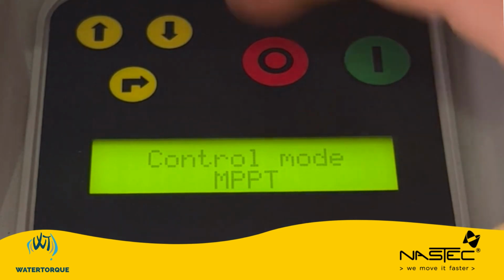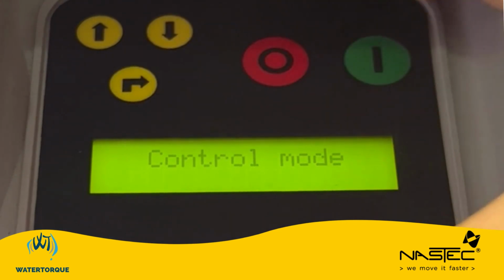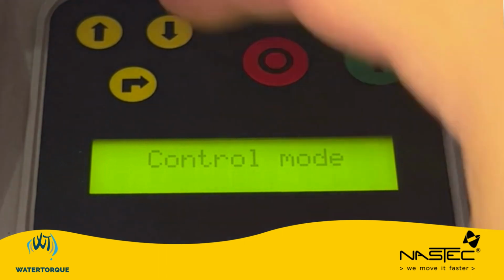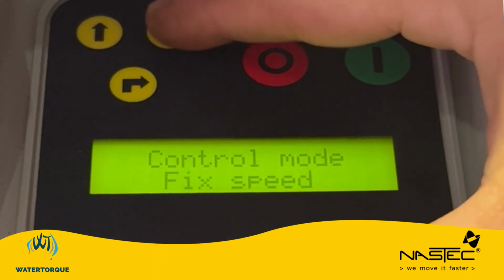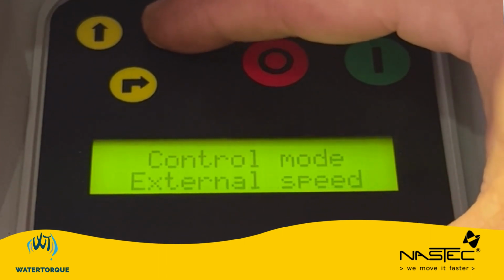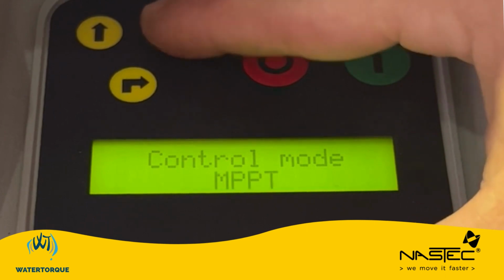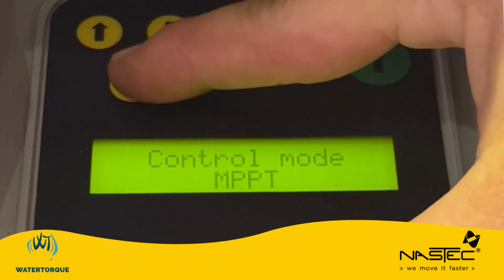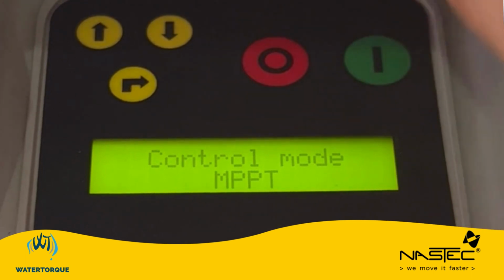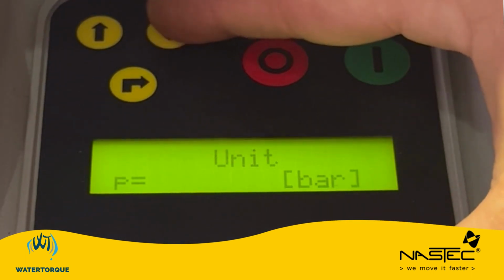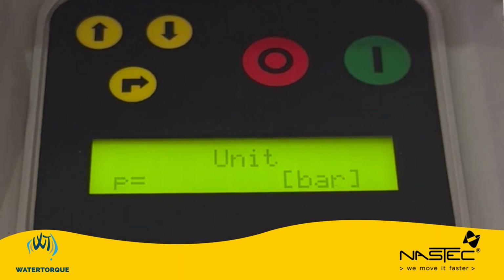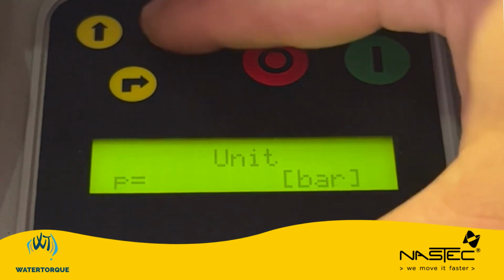If it is not, we hit the enter button, and we'll notice that it starts to flash. Then we can scroll through the different modes that are available within the drive until we hit MPPT. Once we get that, we hit the enter button and it will now stop flashing. Then we scroll down to the next one. We've got units in bar. With this particular setup, we have a pressure transducer, and that is going to be reporting in bar.